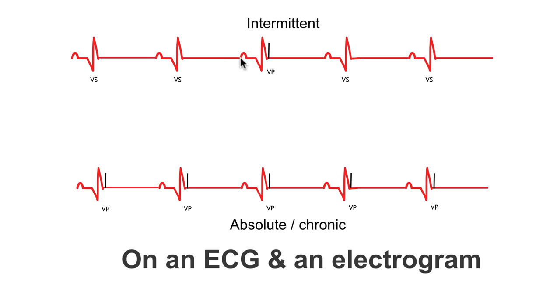However, on the next heartbeat we can see that the atria depolarizes, this is sensed by the pacemaker, it then starts its AV delay, but this time it hasn't registered that a ventricular depolarization has occurred. So what does it do? It tries to trigger a depolarization itself.